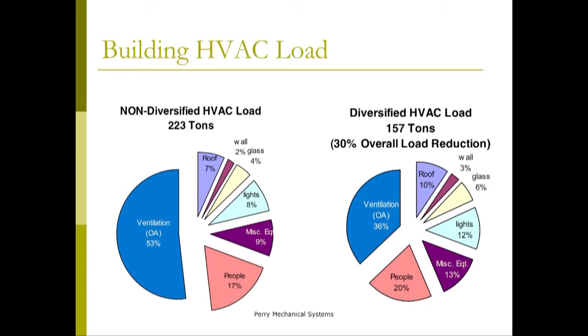The biggest part that gets reduced when you diversify your load is your ventilation air, because of your people. If you were to add them all up in a school, your kids are not in the classroom at the same time. They're in the gymnasium and the band hall and the cafeteria. They move around the school. So if you've got every room full of people and maxed out on ventilation, you can just imagine how oversized your system's going to be.